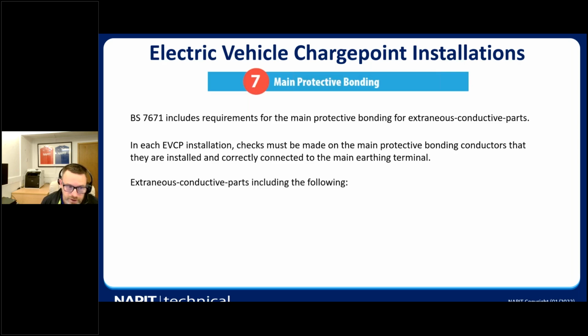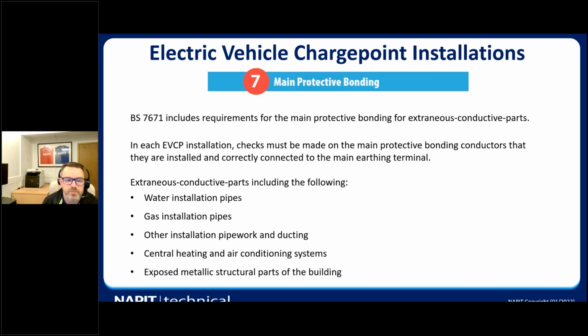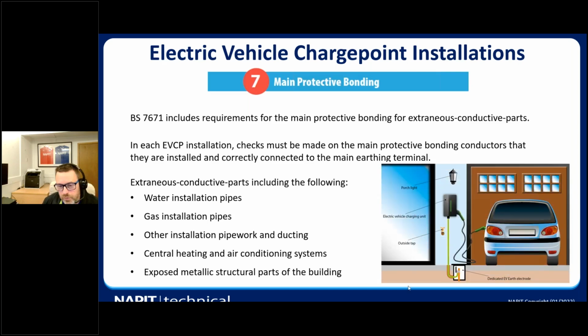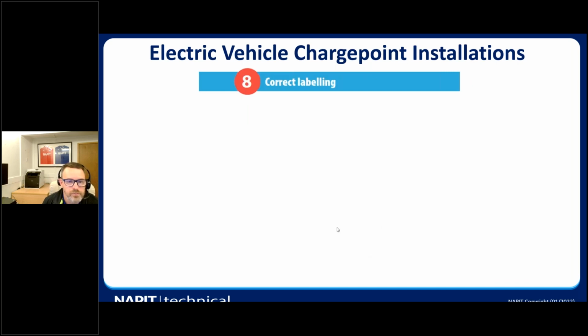The extraneous conductor parts include the following: water pipes, gas pipes, other installation pipework and ducting, central heating systems, and any exposed metallic structural parts of the building. We must make sure all these bonding connections are in place before we start installing the EV charge points. This is just an example of where we have extraneous conductor parts that can be accessible to where the EV charge point is installed.